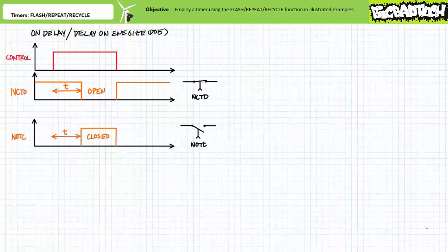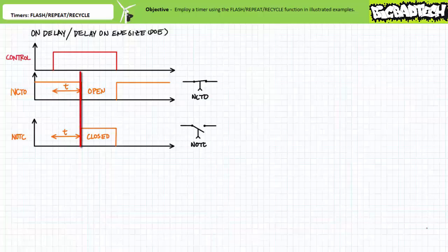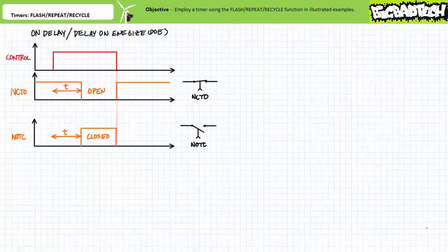A timing diagram of a timer executing the on-delay or delay on-energize function would look like this. When the controlling input is energized, the associated contacts do not instantaneously switch to their opposite state. The normally closed time-open contact remains closed and the normally open time-closed contact remains open. Only after the predetermined delay period T has elapsed do the contacts change states. The normally closed time-open contact opens, and the normally open time-closed contact closes. When the controlling input is de-energized, the associated contacts quasi-instantaneously revert to their normal deactivated state. The on-delay timer could be used to turn another motor on a measurable time period after another has started.